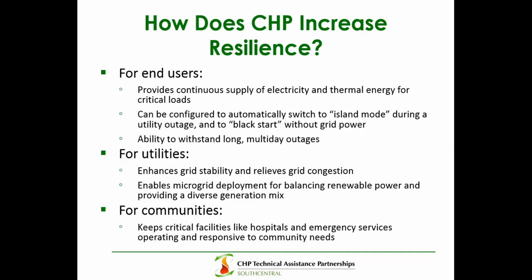So how does CHP increase resilience for end users, meaning people who own and operate buildings, energy managers, facility managers, and so on? The focus here is that CHP can provide continuous electricity and thermal energy for critical loads. It operates 24/7, unlike a natural gas or diesel generator that only starts when the power goes off or there's some disruption, providing a benefit on a continuous basis.